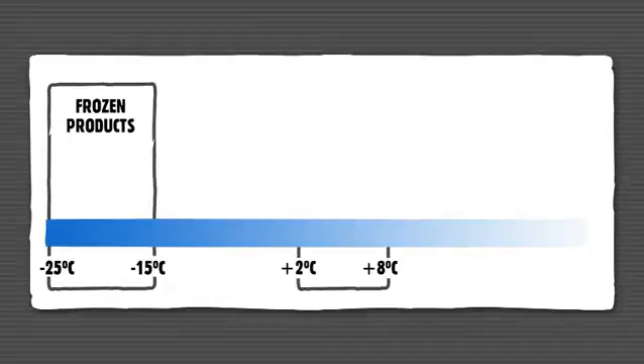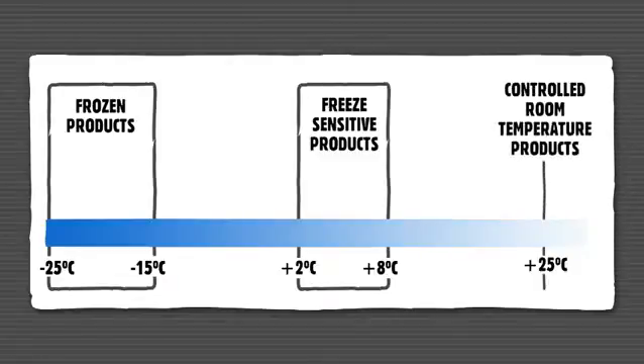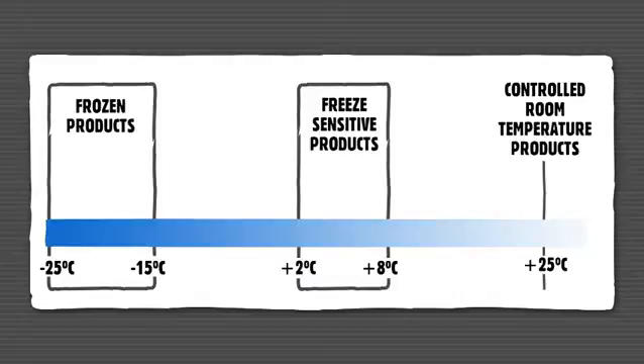There are three commonly used storage temperature ranges for cold-chain products. For products that need to be kept frozen, the typical range is minus 15 to minus 25 degrees centigrade. The vast majority of cold-chain products should be stored at plus 2 to plus 8 degrees centigrade. There are some products which are inherently thermostable but damaged by high temperature, which can be kept at controlled ambient temperatures of around plus 25 degrees centigrade.